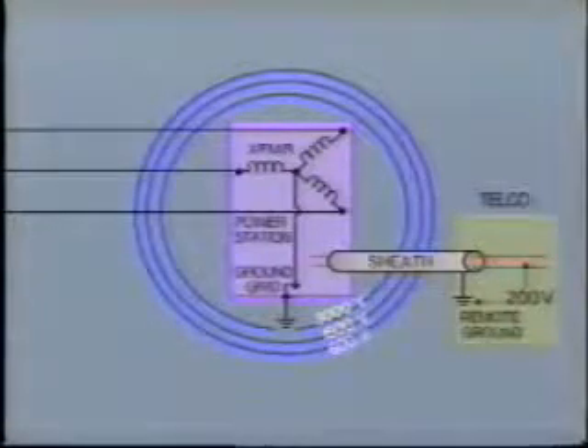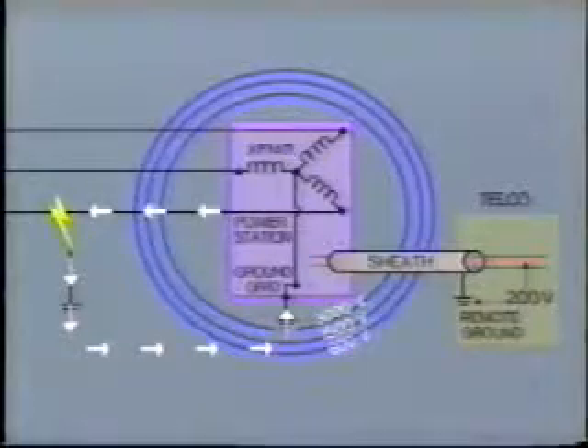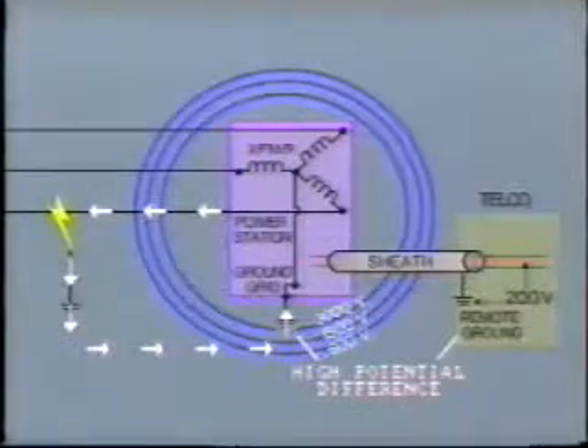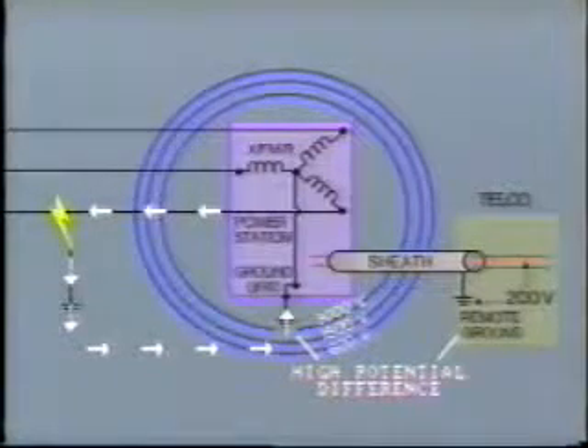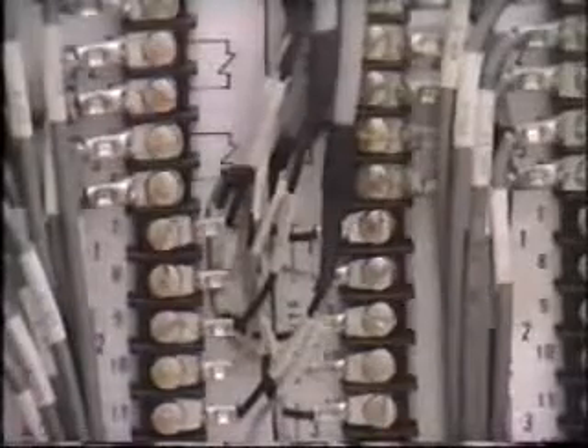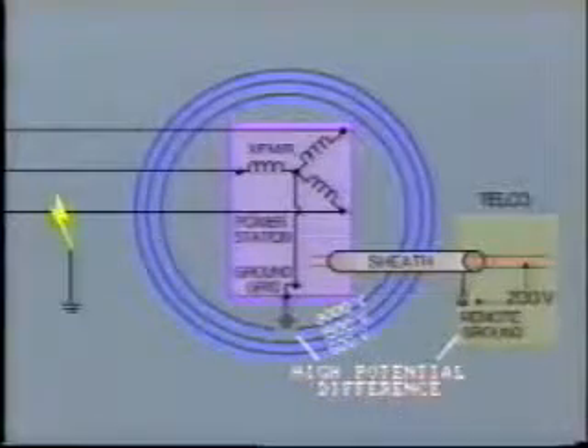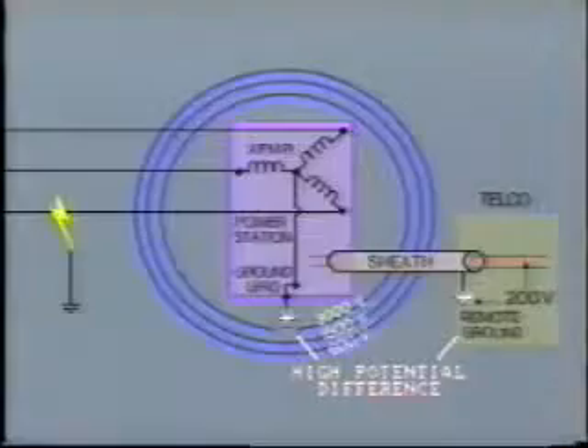This is particularly exaggerated in the case of a line fault when ground current flows through the earth. You will remember that we discussed this matter and associated hazards in an earlier videotape in this series. The point is, you should always be wary of ground connections, particularly on incoming shielded cables. Shielding is necessary on control wiring and communications circuits to minimize interference from nearby electromagnetic and electrostatic sources. If the shield is grounded at the remote end, it may offer a high potential difference to ground in the local station. For more information on this subject, refer to videotapes 19 and 20 in this series. A typical guide for shielding and grounding is included in your workbook.